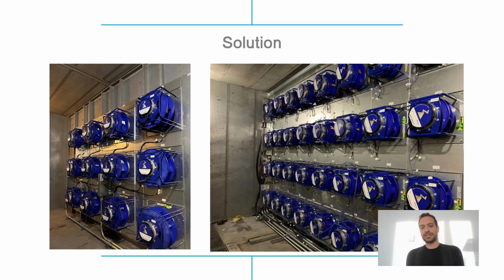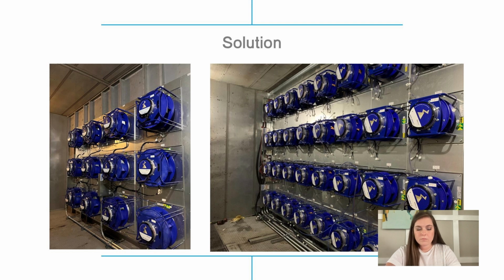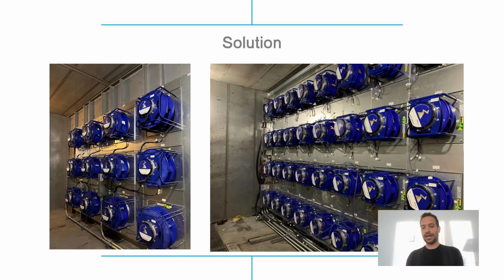Because of the number of fans that we had to go with on the supply side, we actually had to provide these with 2 control panels. So we went with 2 sections, and each section would be 16 fans, and each 16 fans would have its own power and control connection. So it gave them another layer of redundancy as well, which actually worked pretty well for them. So if anything happened to the controls, it still has some redundancy in that fan array until they had a spare part, so they could replace that in a matter of probably an hour.